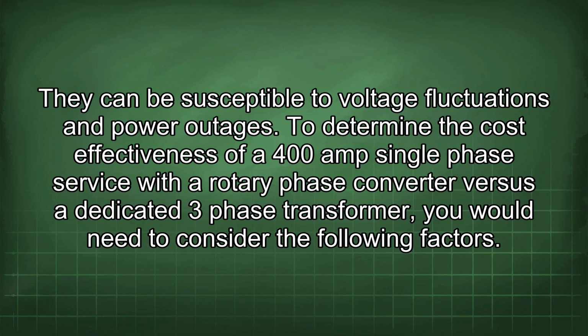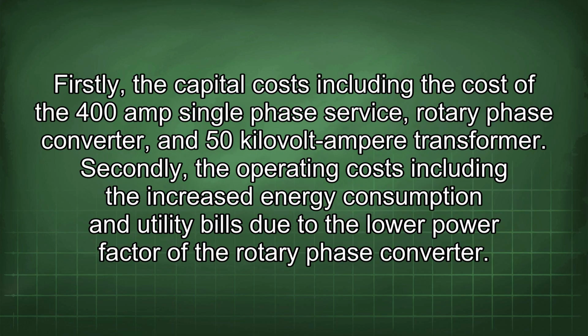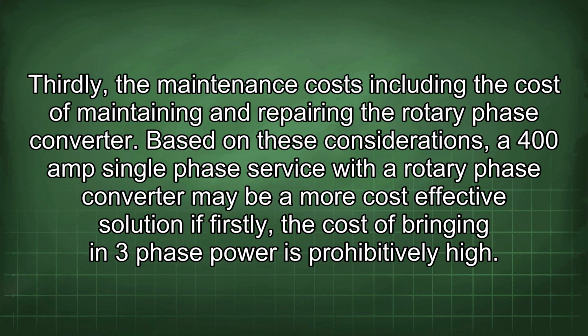To determine the cost-effectiveness of a 400 amp single-phase service with a rotary phase converter versus a dedicated three-phase transformer, you would need to consider the following factors. Firstly, the capital costs, including the cost of the 400 amp single-phase service, rotary phase converter, and 50 kVA transformer. Secondly, the operating costs, including the increased energy consumption and utility bills due to the lower power factor of the rotary phase converter. Thirdly, the maintenance costs, including the cost of maintaining and repairing the rotary phase converter.